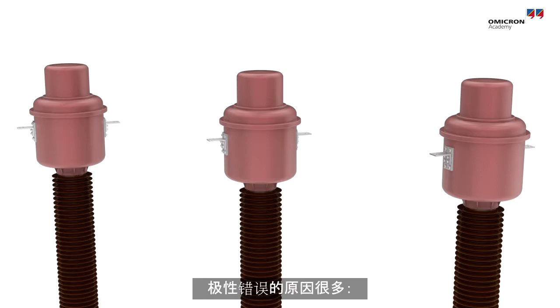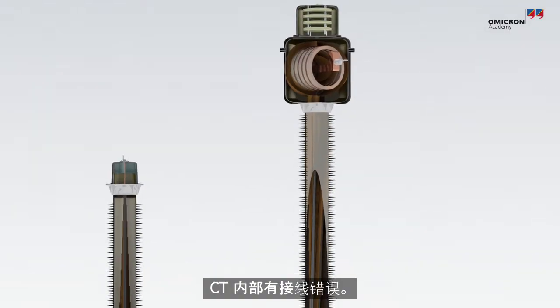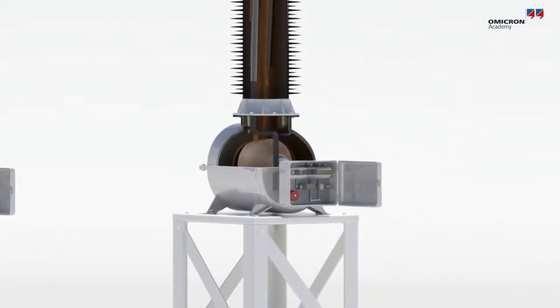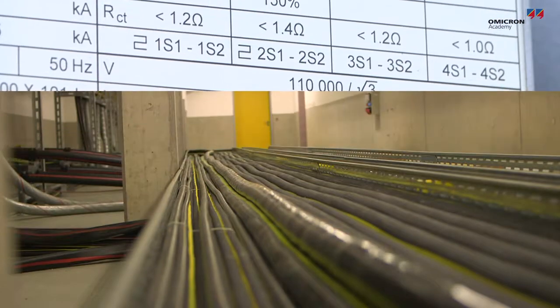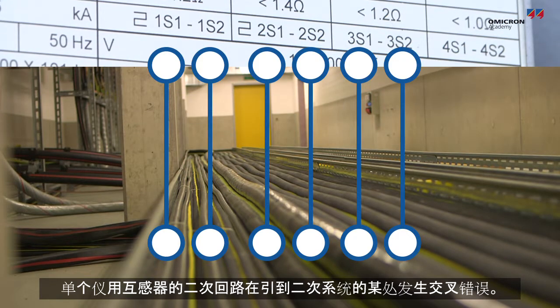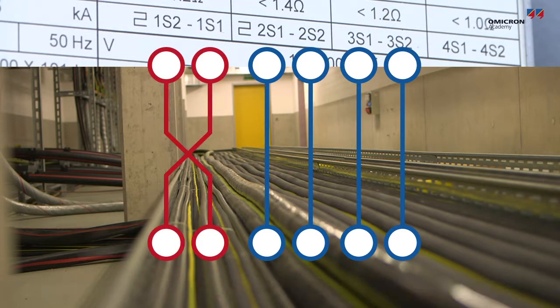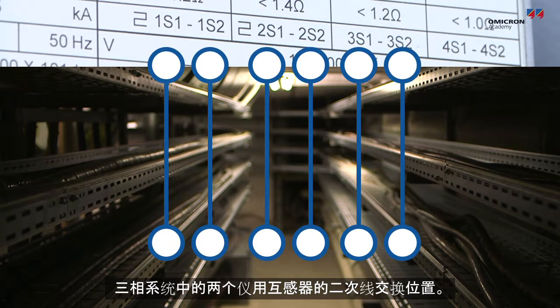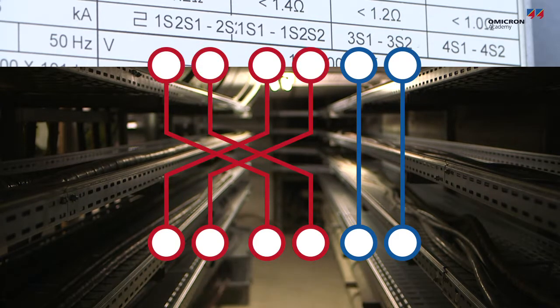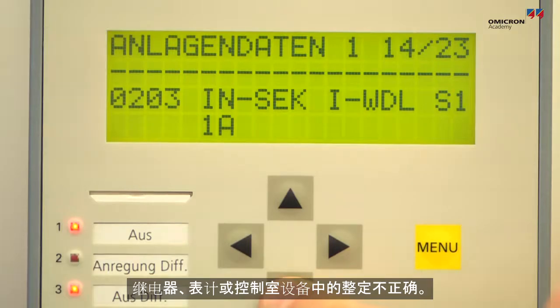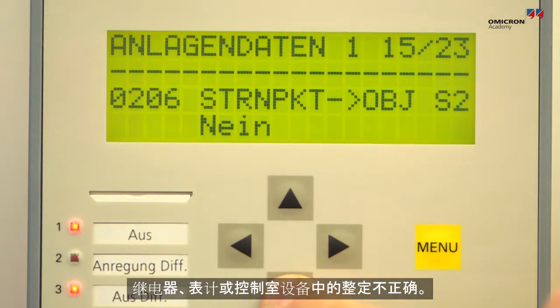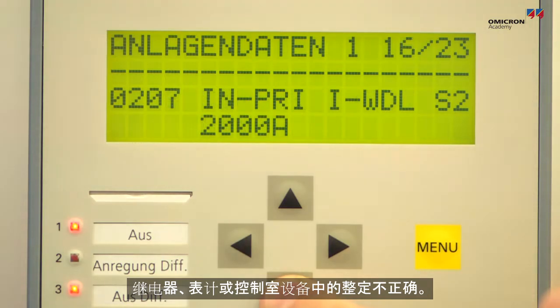There can be many reasons for improper polarity. The CT might have been installed with the wrong mechanical orientation. A CT could have an internal wiring error. A single instrument transformer's secondary wires may have been crossed somewhere along the way to the secondary system. The secondary wires from two of the instrument transformers in a three-phase system may have been swapped. The settings in the relay, meter, or control room device may have been set incorrectly.